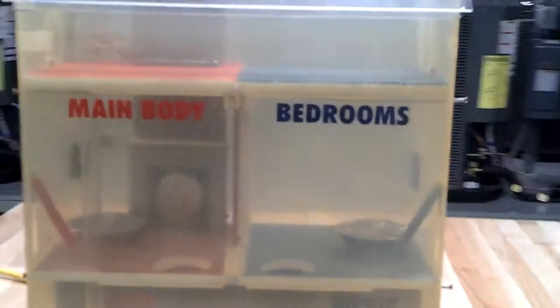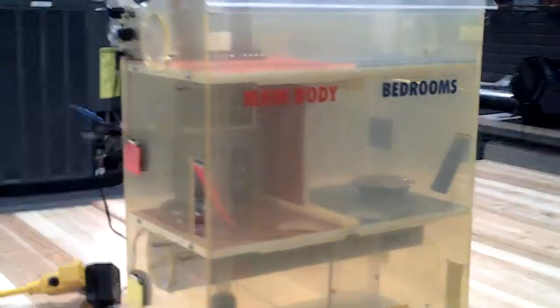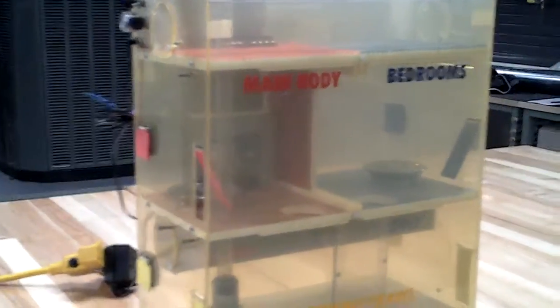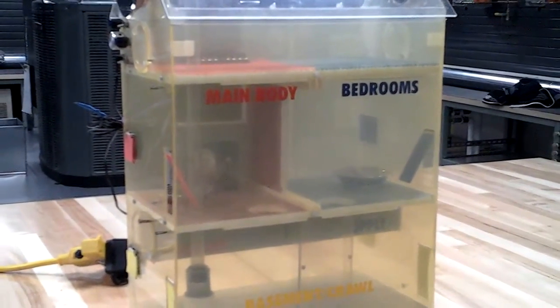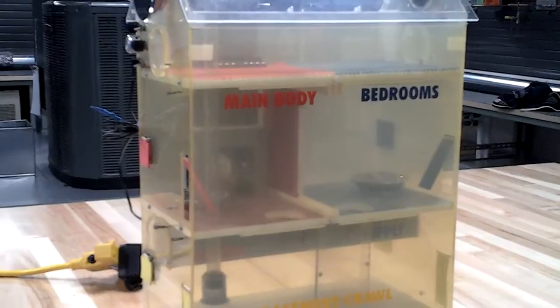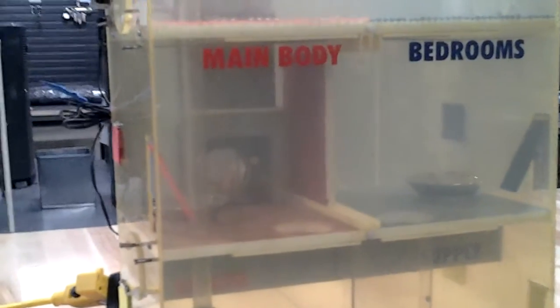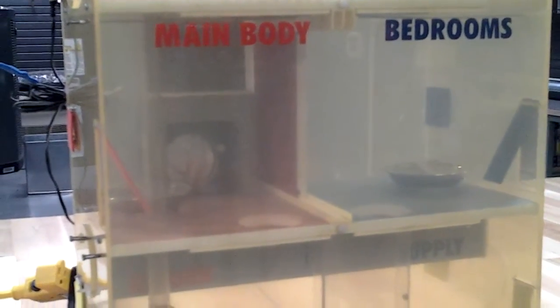Supply air lost to the outside causes the return to starve for the air lost, thus depressurizing the house to make up the air lost. Untreated outdoor air will then infiltrate a building when indoor pressure is less than the pressure outside. An excessively negative indoor pressure, as we see here, can cause problems, such as hindering your ability to effortlessly open outward swinging doors, because the negative pressure wants to keep the door sucked into the house.